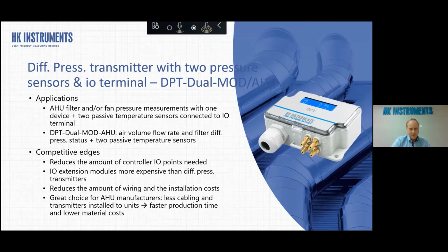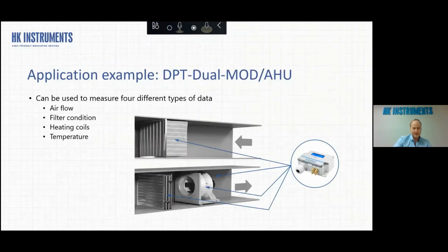So as said before, it reduces the amount of I/O points on the controller side. So you can use a cheaper controller, and it also reduces the amount of wiring and the installation cost to make the production more lean. And here is an application example once more about the DPT dual mod. So as said, you can measure the filter, the fan, and 2 temperatures.